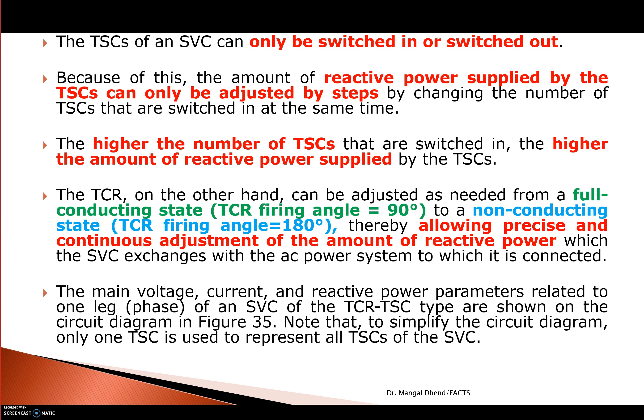TSC in an SVC can only be switched in or switched out — it will not give smooth variation like TCR. Either a TSC will be on or off, and reactive power supplied by TSC can only be adjusted in steps: 10, 20, 30. You cannot get 27 directly from TSC alone. Higher the number of TSCs switched on, higher the reactive power supplied. If 3 banks are on, power is 30, and TCR firing angle must be 180 degrees so TCR is off.